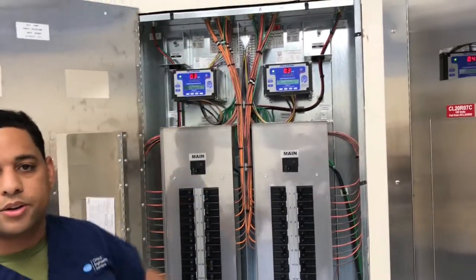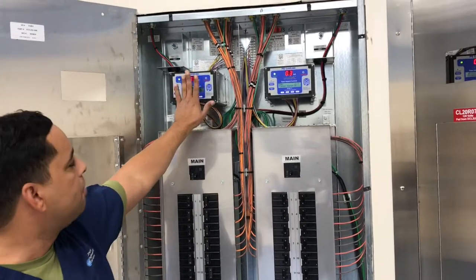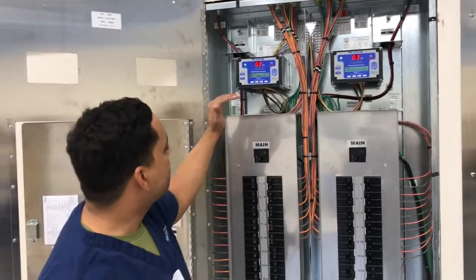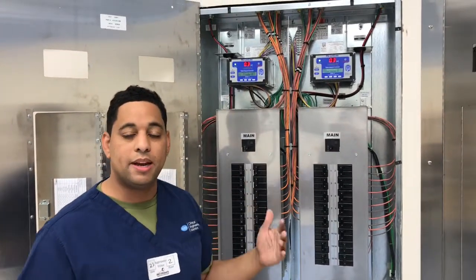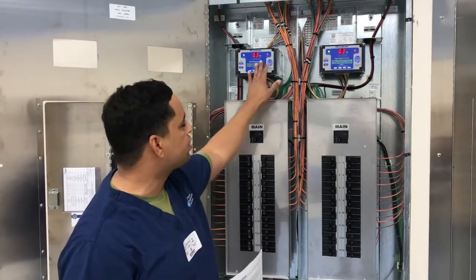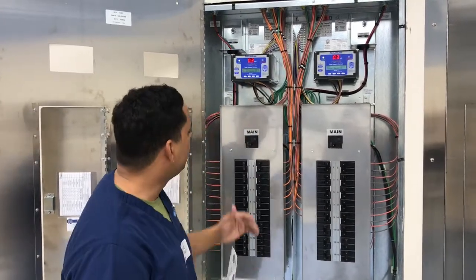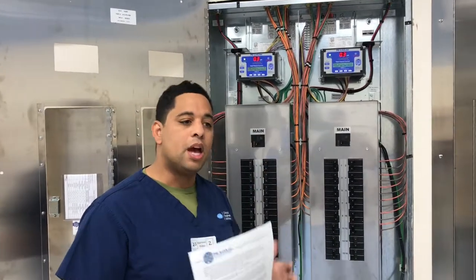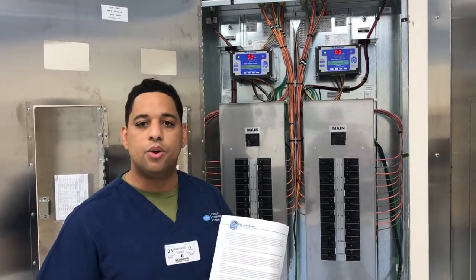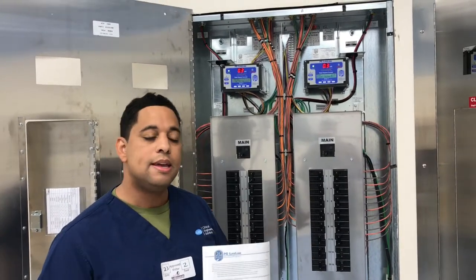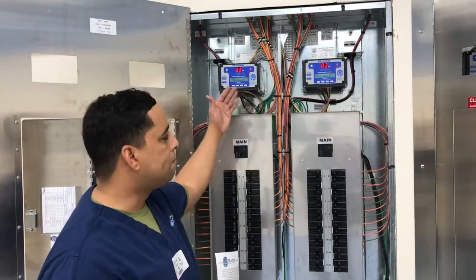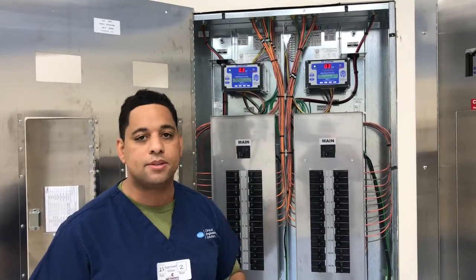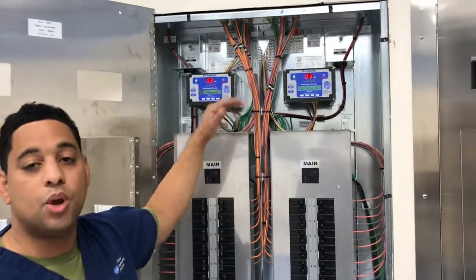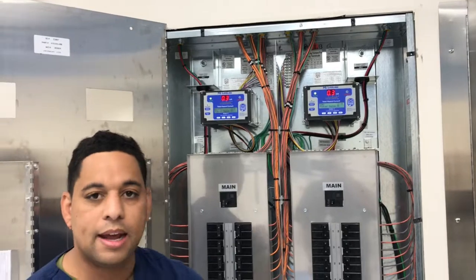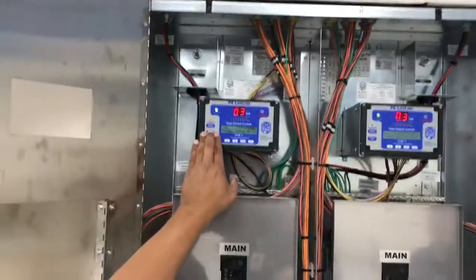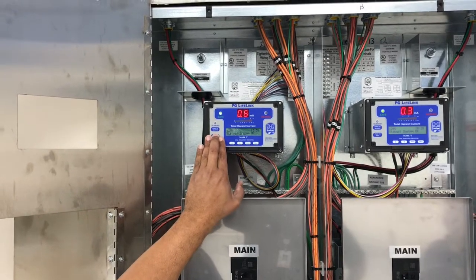Right now, all of these wires are being measured for leakage, and this is your monitor to calculate that. Now, right now we're at a very low level of leakage, but as equipment is brought in and added, this number is going to go up and up and up. And so, at a certain point, it becomes a possible hazard, even though the chance of shock is very much reduced. It becomes a possible hazard if it goes above 5.0 milliamps. And so this monitor is reading for that, and it will alarm when it gets to that number. And I can demonstrate that for you. So if you hold your test button, it will go all the way up to 5.0, and then it will alarm.